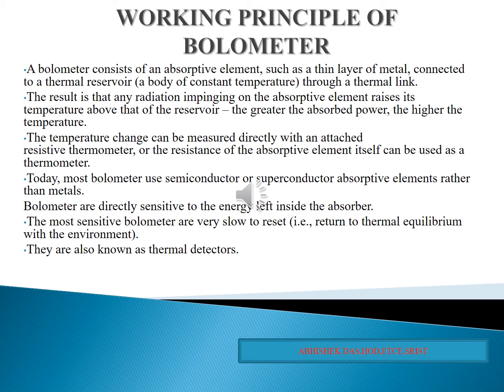The element absorbs the power and is heated, which causes a change in resistance, thereby unbalancing the bridge. The imbalancing is in the direction opposite to that of the initial cold resistance. This action causes the output from the oscillator to decrease so as to effect a balance. The EVM circuit, or electronic voltmeter circuit, measures the amount of this power decrease from the oscillator and displays the measurement as the power increase supplied by the microwave field.